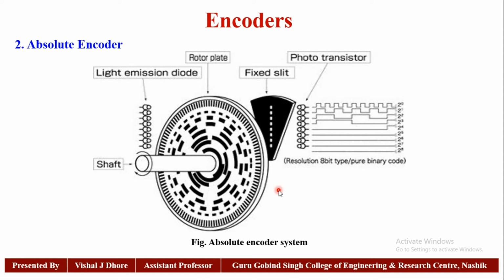After counting a single bit or by decoding a set of bits, the pulses can be converted to relative or absolute position measurements. Encoders have both linear and rotary types, but the most common type is rotary. Rotary encoders are manufactured in two basic forms: the absolute encoder, corresponding to each rotational position of the shaft, and the incremental encoder, which produces digital pulses as the shaft rotates, allowing measurement of relative position of the shaft.